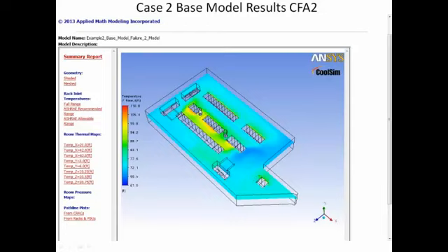layout. Okay? So you give me a geometry layout, however it's laid out, and we will be able to find for you the optimal operating point through scenario modeling, where you say, what is the optimal point? And I think you could go into a data center and configure it that way and get very, very close to being right where you want. And Magnus, I would argue that as we move towards these control systems where we have sensors under the floor and sensors here and sensors there that are all, by the way, sensing something on their own and controlling fan speeds based on that, the idea of knowing what the optimal design point should be when you enter the room to set that stuff all up is going to become critical, wouldn't you think?